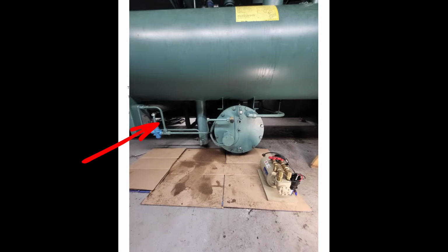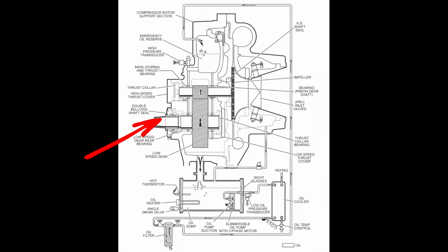Either way, without getting into the weeds here, the metering valve has a sensing line on the oil temp leaving. So basically, as the oil temp increases, the valve should be opening, and then as the valve opens, more cooling is put to the oil, and it slows down, which you can see right here, right? So this is our oil entering line. We have our oil leaving line. There is a sensing bulb here, and then this is controlling how much flow goes through the cooler, and then this goes back to the evaporator. So this is coming off of our liquid drop leg coming out of the condenser.